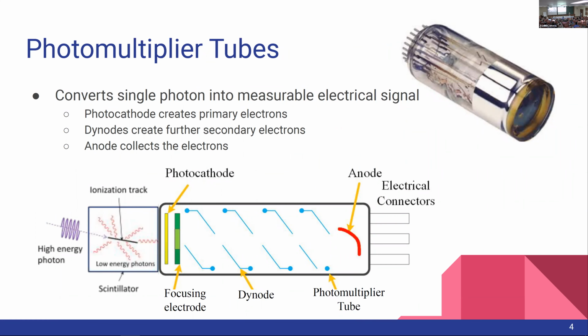So what is a PMT? Well, hopefully you all know this by now, but I'm going to do an overview anyway. It's an electrical device that converts photons into detectable electrical signals. So we have our photon from the scintillator, and it goes into a PMT and hits this photocathode, where you'll get an electron due to the photoelectric effect. Then we have an electric voltage through the PMT, which will accelerate the electron to the first dynode, where it will create secondary electrons. These secondary electrons will go to the next one and create more electrons, and we do this multiple times. This was supposed to be a nice animation, but it didn't work. So you just have to imagine that yourself.